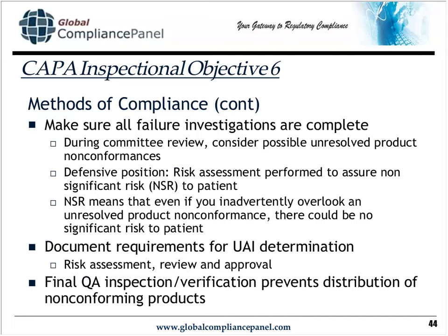And I like to take at times a defensive position when I look at failure investigations from a risk assessment perspective. I perform a risk assessment to make sure that the risk to the patient is either absent or at worst insignificant. And I use that when I speak to the FDA when they inquire as to how I address risk assessment during my failure investigations.